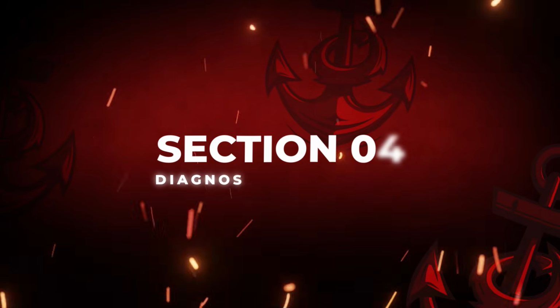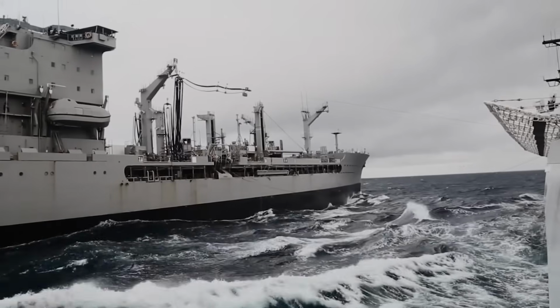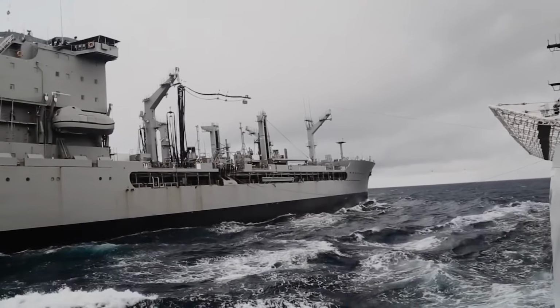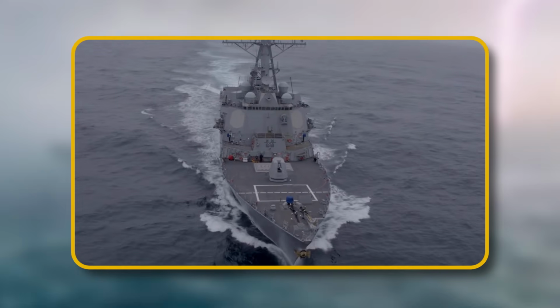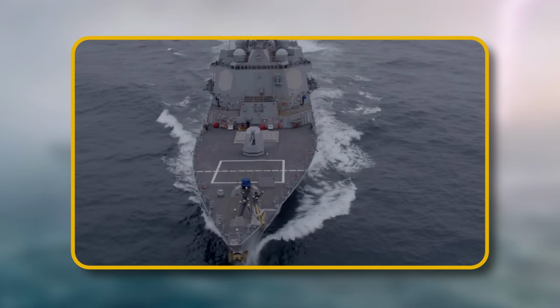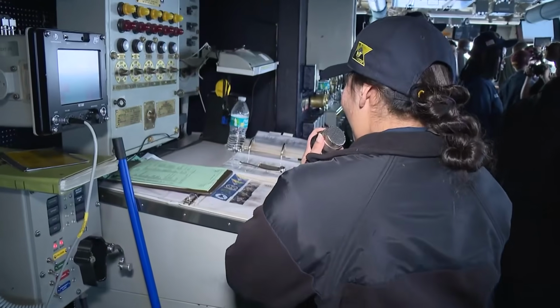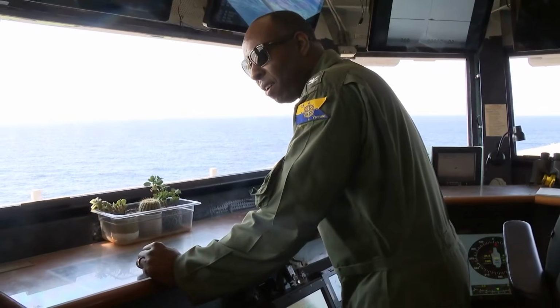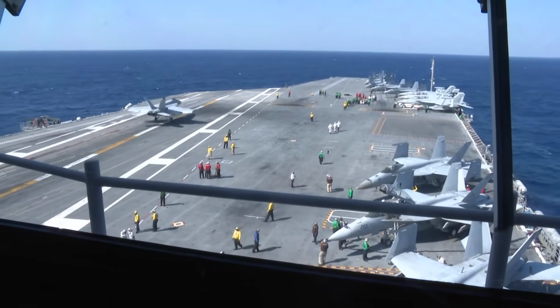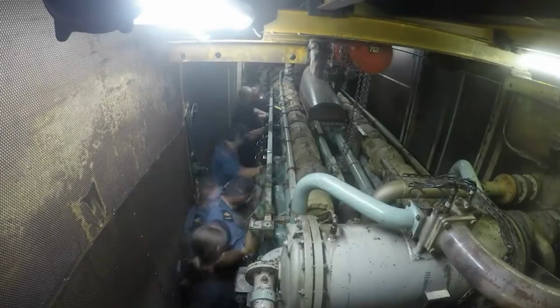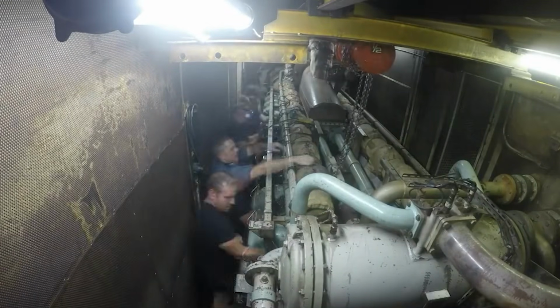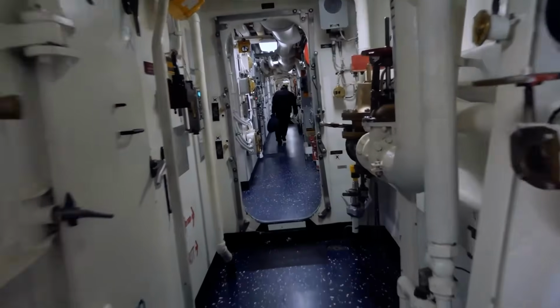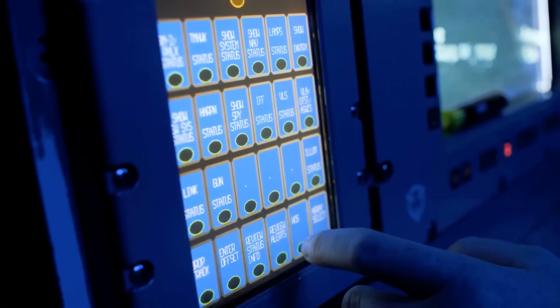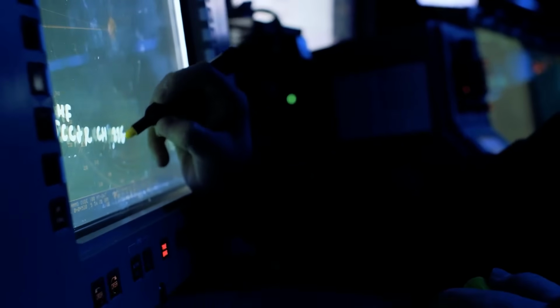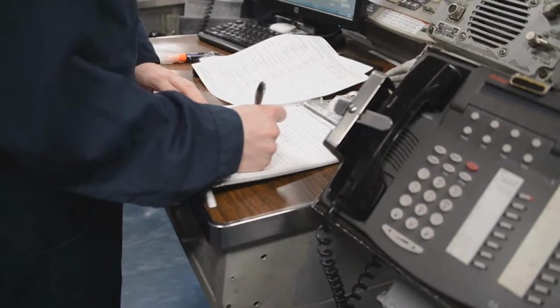Section 4. Diagnose like a doctor. Once the space is safe enough to enter, you get clinical. You trust symptoms that do not lie. Sound, vibration, smell, heat. Cavitation talks different than a bad bearing. Burnt insulation smells different than hot metal. You read gauges, then cross-check because one bad sensor can steal time. You chase patterns, pressure oscillation, temperature drift. A breaker that trips, resets, then trips again. Suction pressure that drops like a clogged strainer. Amps that creep up like a motor is fighting load.